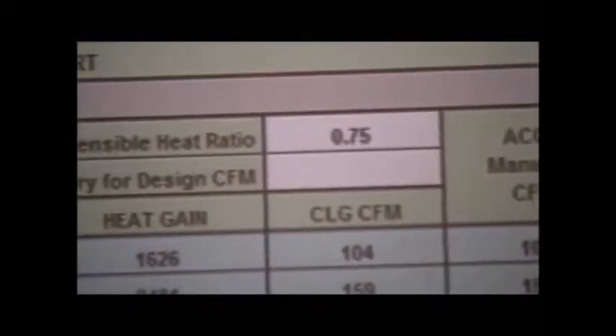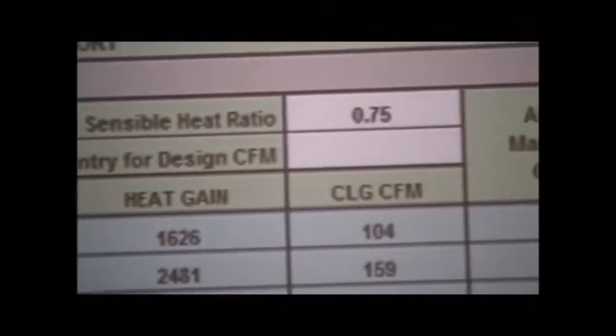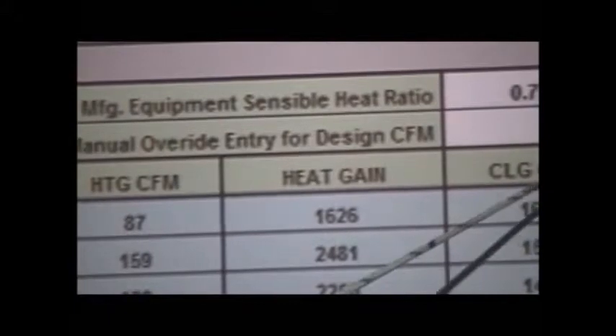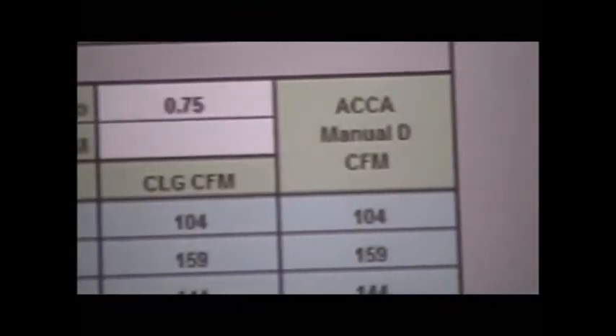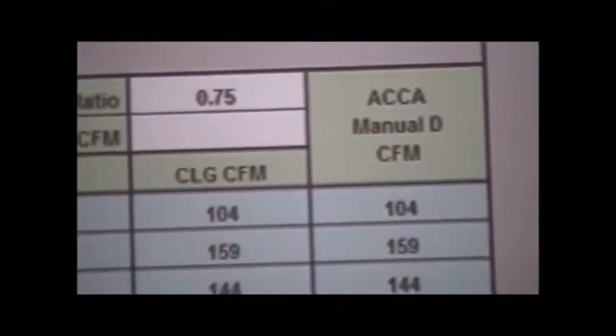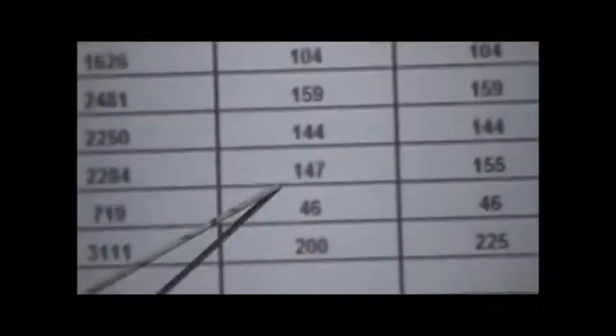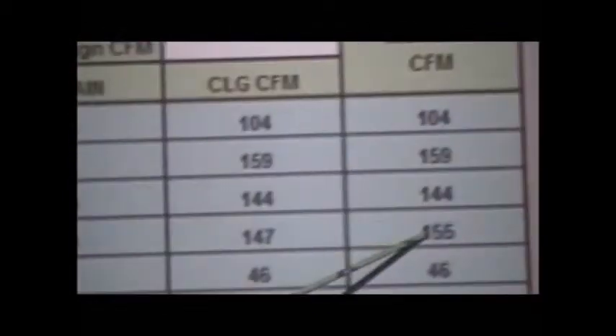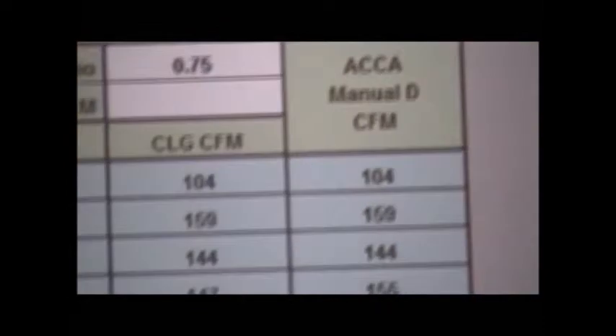There's a little bit of confusion in the world that says you should use the cooling CFM for your duct design. That is false. You need to use the largest CFM, whether it be heating or cooling, for your duct design. We're not talking about equipment design — we're talking about room by room duct work. You'll notice this is an example: we only have 147 CFM required for cooling, but yet we have 155 required for heating for this particular bedroom. According to the ACCA, they tell you to use the 155.